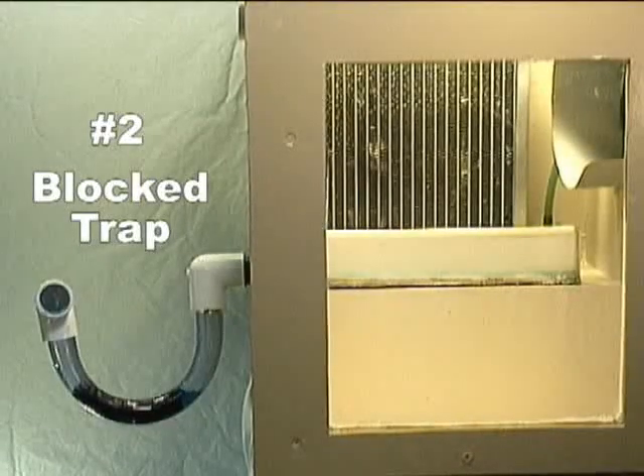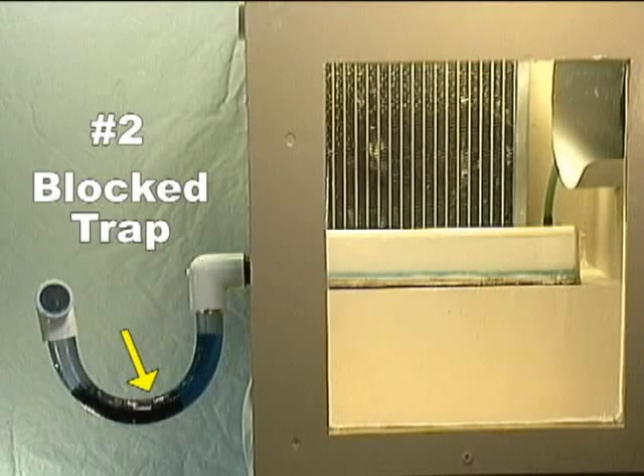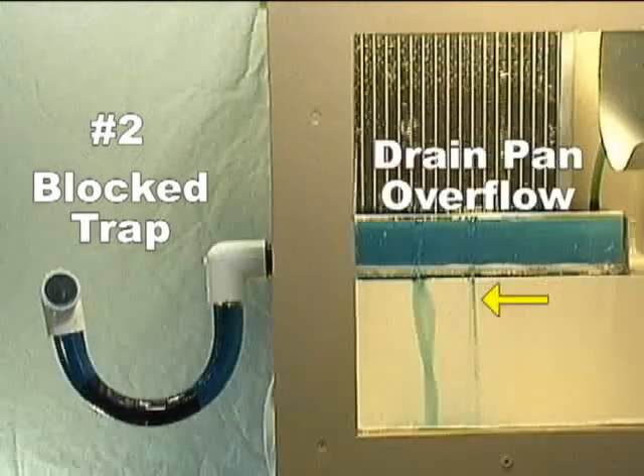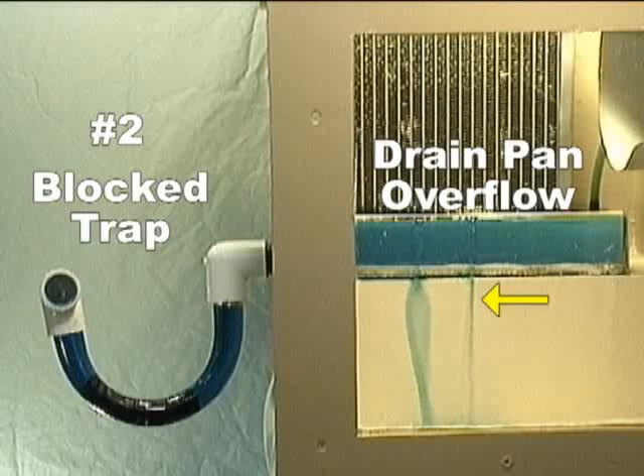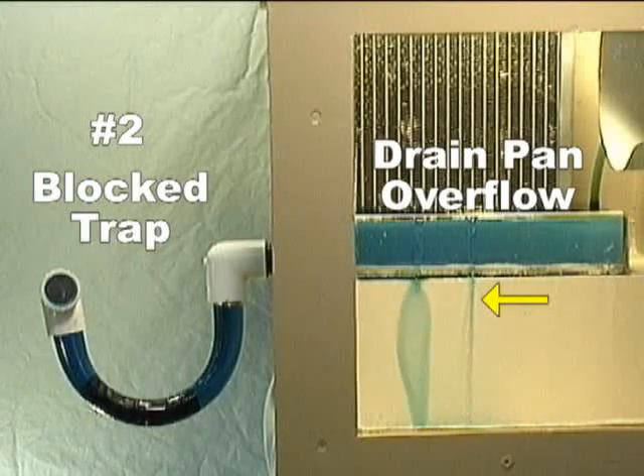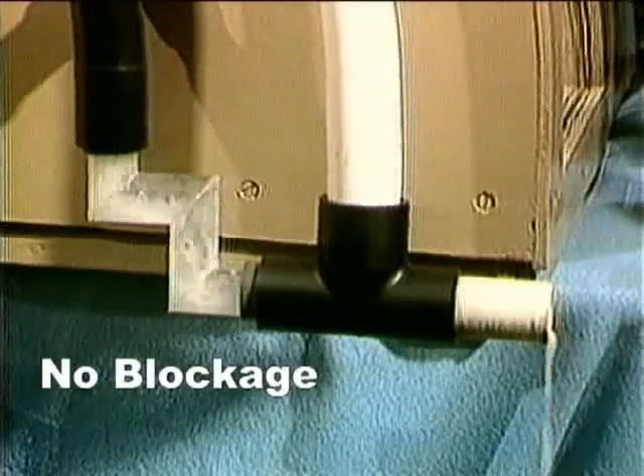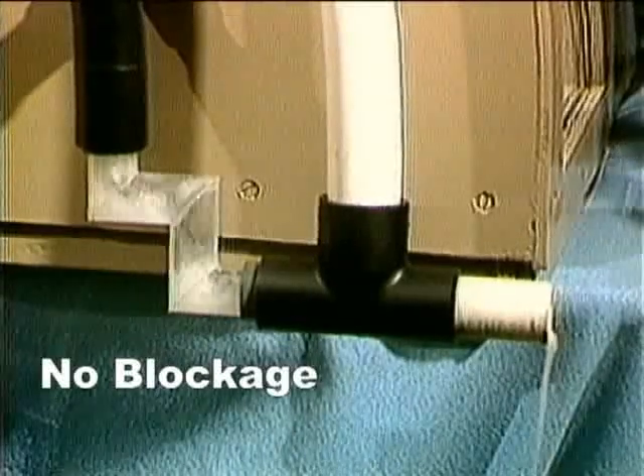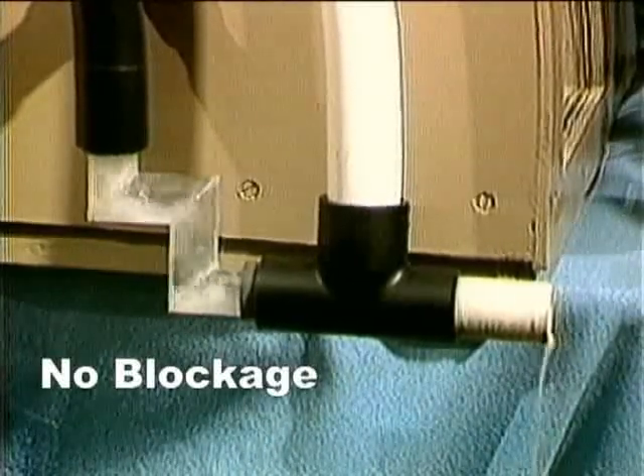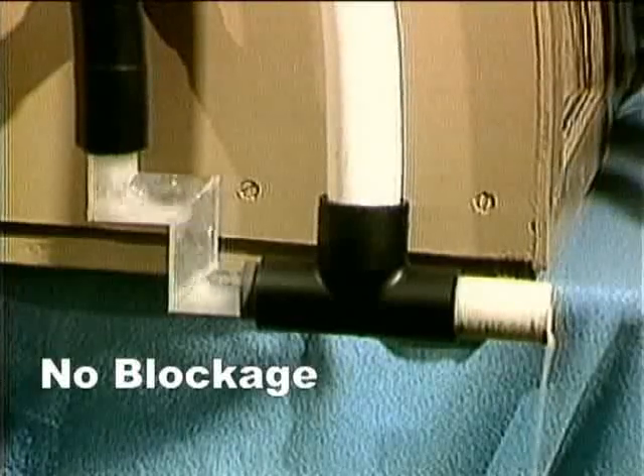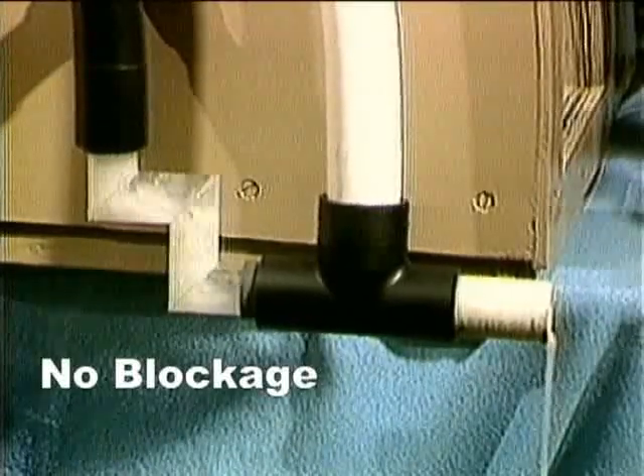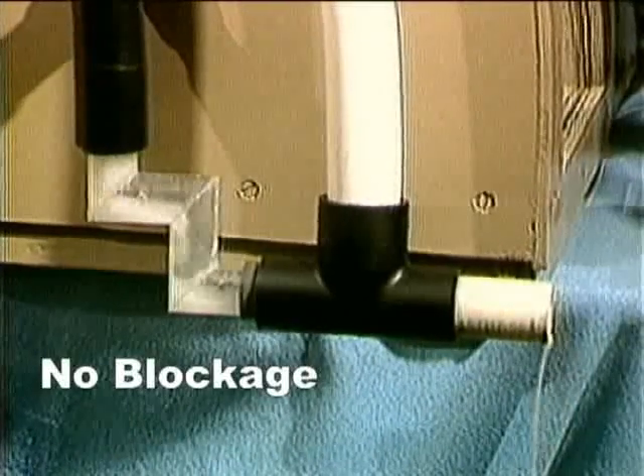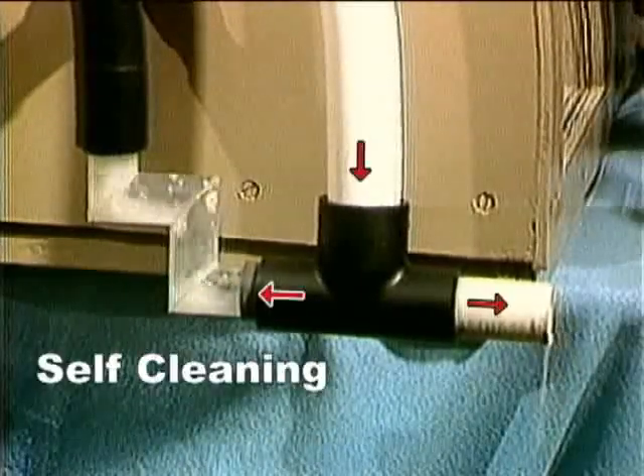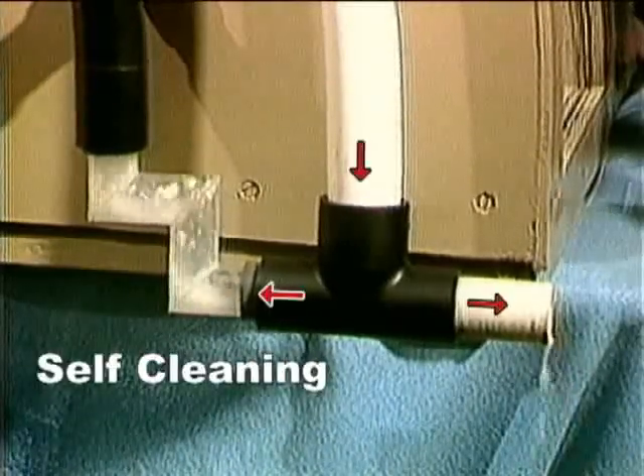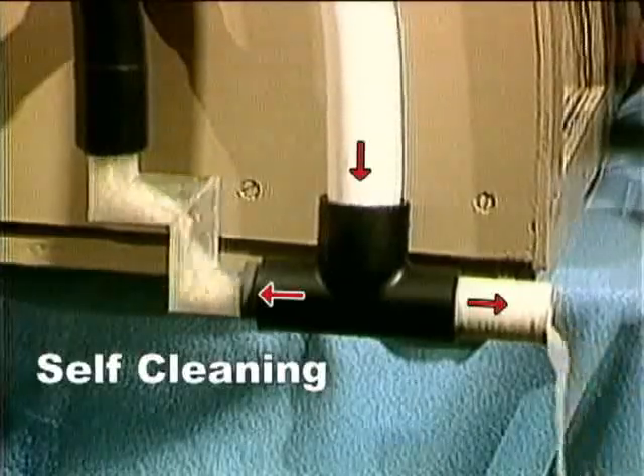One of the most common problems with condensate traps is that they support the growth of algae, catch debris, and become blocked, causing drain pan overflow. This happens frequently, often less than 6 months after P-trap installation or cleaning. The CostGard Condensate Drain Seal inherently guards against such blockage. This special CostGard device, equipped with clear plastic elbows, shows why. Here, soggy oatmeal is used to simulate the slime that often clogs drain lines and traps. Note the self-cleaning action produced by the air entering the device and the rapid passage of the debris.